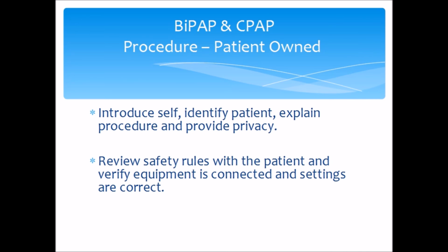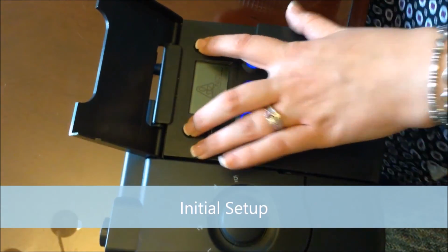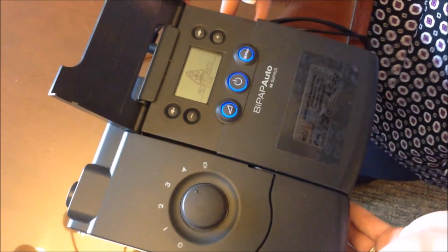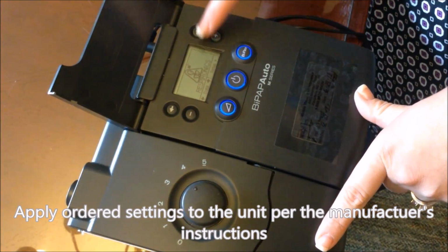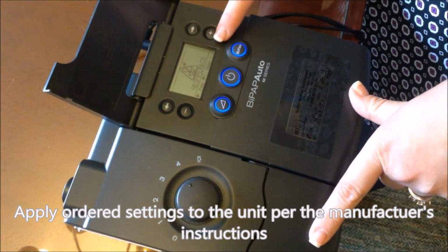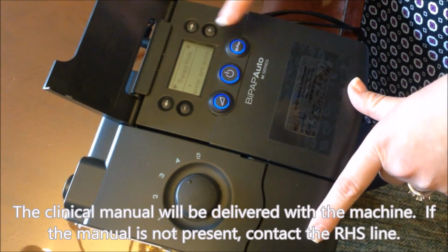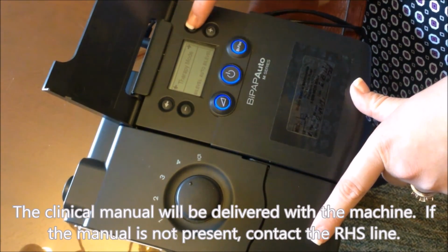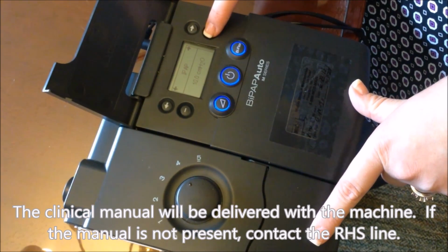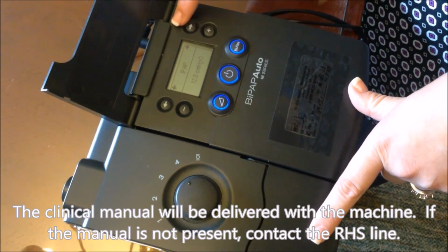Introduce yourself. Identify patient. Explain the procedure and provide privacy. Review safety rules with the patient and verify equipment is connected and settings are correct. The initial setup. Apply ordered settings to the unit per the manufacturer's instructions. The clinical manual will be delivered with the machine. If the manual is not present, contact the RHS line.